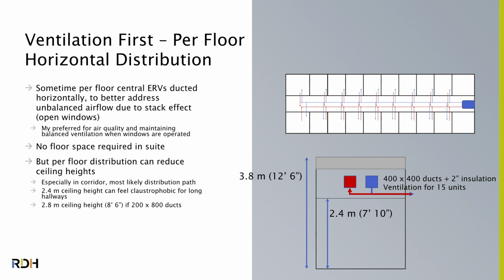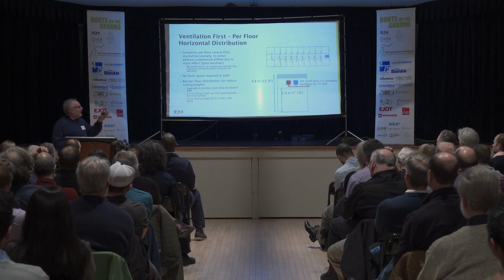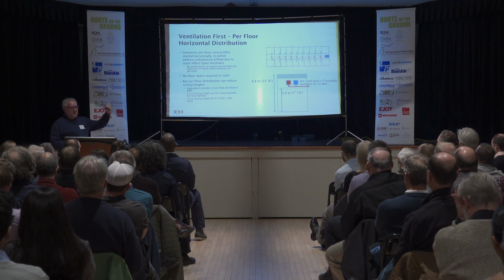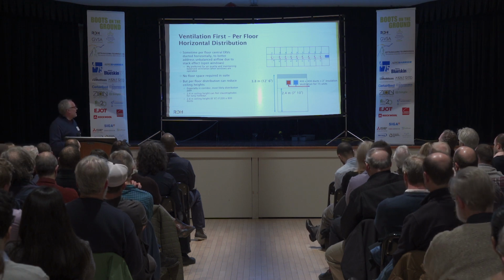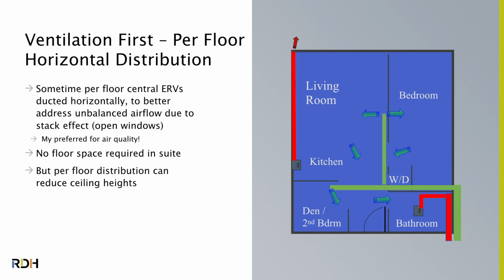It does still minimize the amount of outside air ducts that are part of our heat loss. It means you've got to find some space architecturally, and we actually have an old project that was done for Lee that did this in Regent Park. Because the distribution is often in the corridor, that ceiling starts getting a little low. And when it's a 200-foot long corridor that's only at 7'10", it starts feeling a little cave-like. So that is one of the challenges of doing that distribution, but there it is. And now, of course, the distribution of suite is kind of similar, except we can now tie it to the corridor.